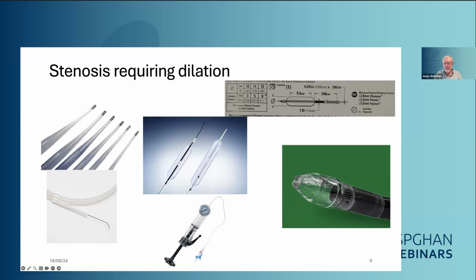These balloons are also very clever tricks, because we pass the balloons through the channel of the scope, so they are deflated when they get there. Then we inflate up to a certain pressure, and this creates a predefined diameter. As you can see here, these balloons have variable distension diameter. So if you use this one, if you use 3 atmospheres, then you'll have 10 millimeters diameter. If you blow up to 5, and we use these devices to blow up the balloon with this manometer to control the pressure, you'll get 11 millimeters. If you go up to 8, you'll have 12 millimeters diameter.